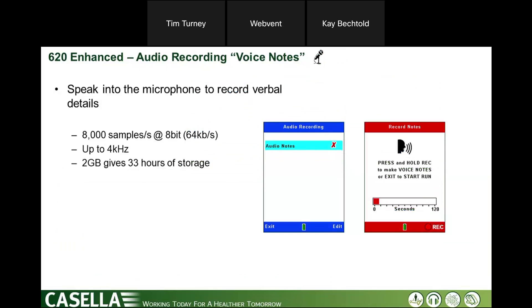Audio notes can be switched on or off. When switched on, the instrument automatically prompts you to record an audio note when you start a measurement. It has a two-gigabyte memory, which is enough for 33 hours of audio storage — sufficient for an audio note on every one of the 999 runs the instrument can store.